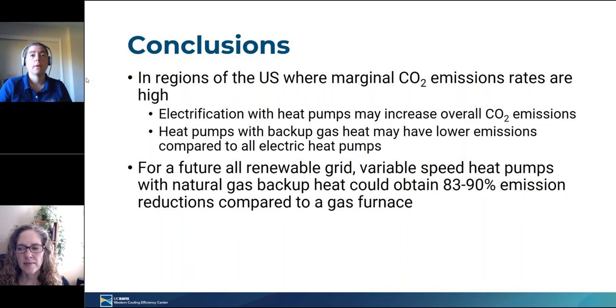Well, okay, so here's what I'll say, that's not at all how the systems operate in the field. The heat pump will run, and when it needs additional help, the electric heat will kick in to give it whatever the shortfall in the capacity of the heat pump is. But if you assume that the heat pump turns off completely, now you're going to have a COP of 1, which is terrible system performance, and that's going to really penalize you. So you really want to run the heat pump as much as possible because it has a high COP.